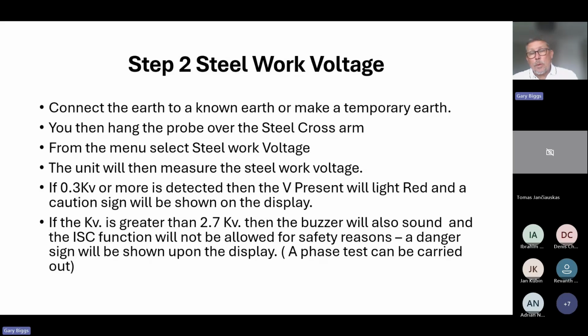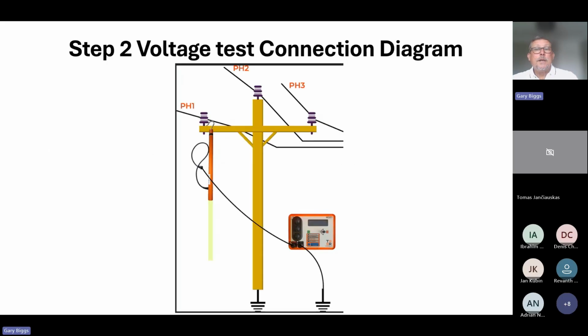If it sees 0.3 to 2.7 kV, then you will want to know what is the potential milliamp that's there, the danger level, as it were. If the kV is greater than 2.7, it becomes a bit of a moot point worrying about the milliamps. You know that this is a hot site, this is a hot problem, and it needs to be sorted. So you would go straight to checking which of the phases is shorted or effectively broken down to the metal crossarm.